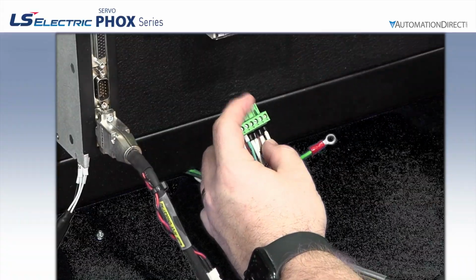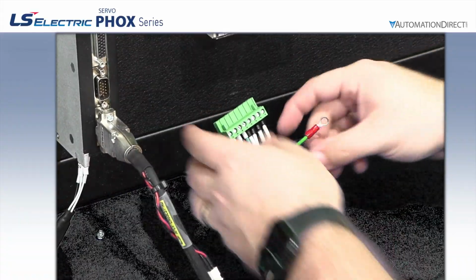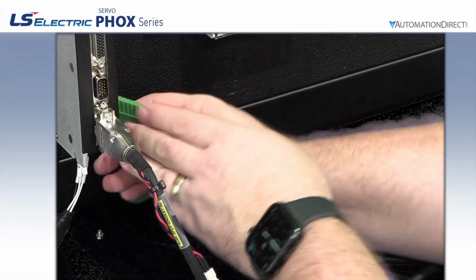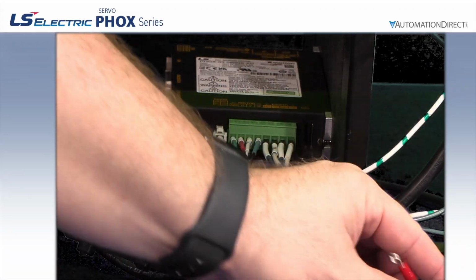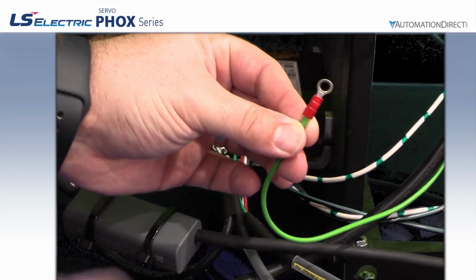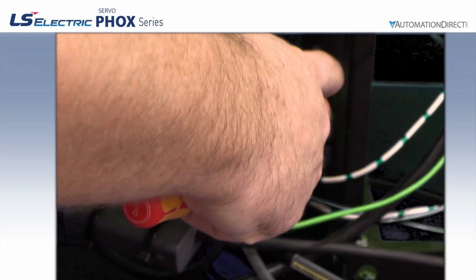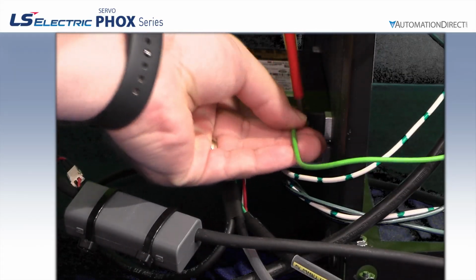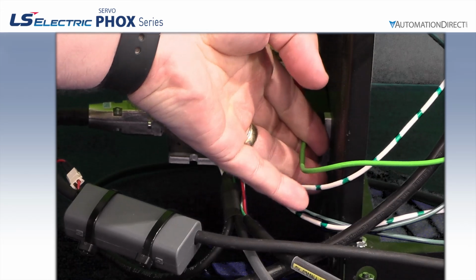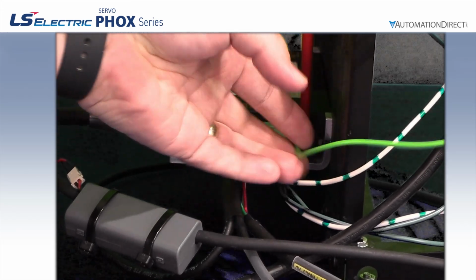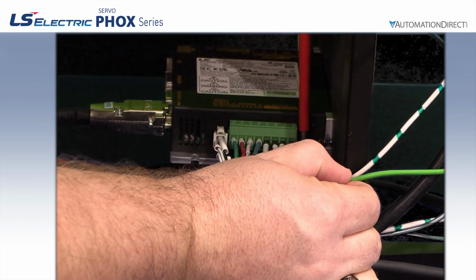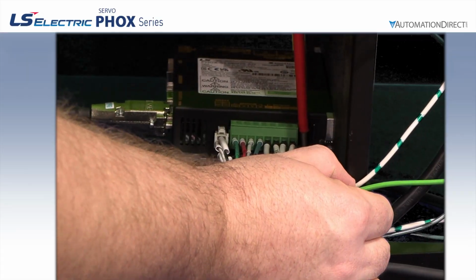Once everything's tightened and verified against the drive label, reconnect the green terminal block into the drive. Be sure to also connect the drive ground to the ground terminal block at this point. Even during basic testing, an ungrounded system can be unsafe and may cause irregular behavior.